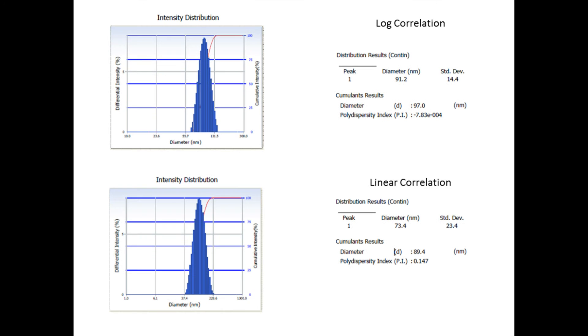The top intensity distribution is log autocorrelated, while the bottom distribution is linearly correlated, and you can see that in this case, the log autocorrelator diameter and standard deviation results is closer to the standard size of 100 nanometers than the linear autocorrelator results. This data is centered with no skew.